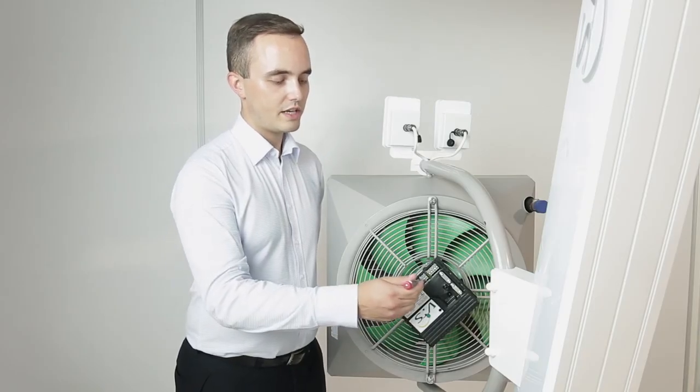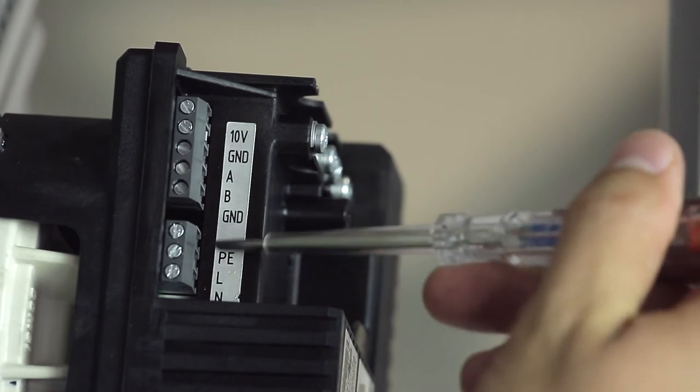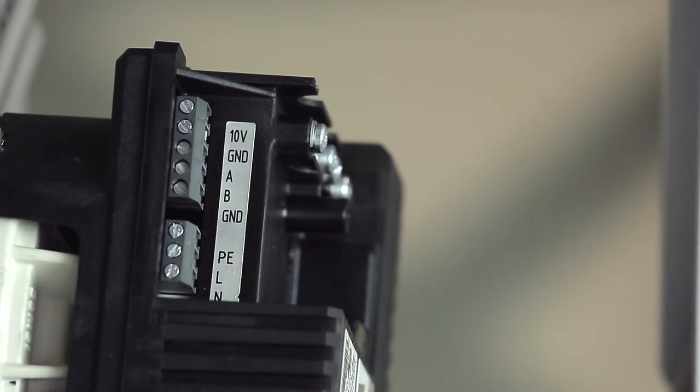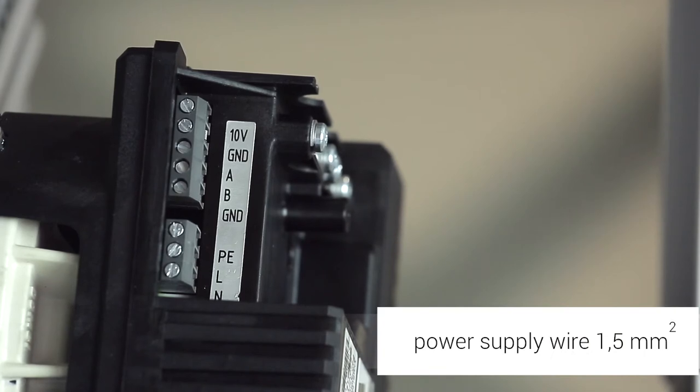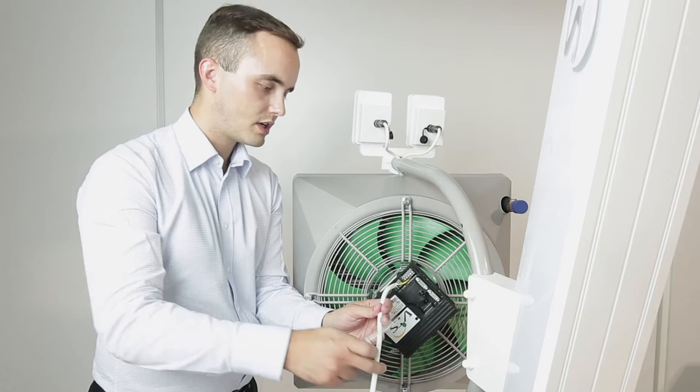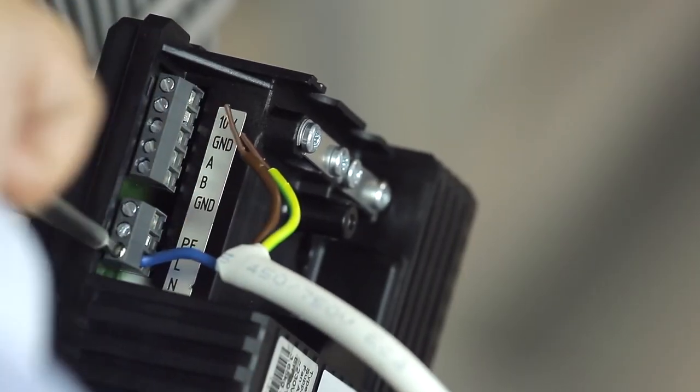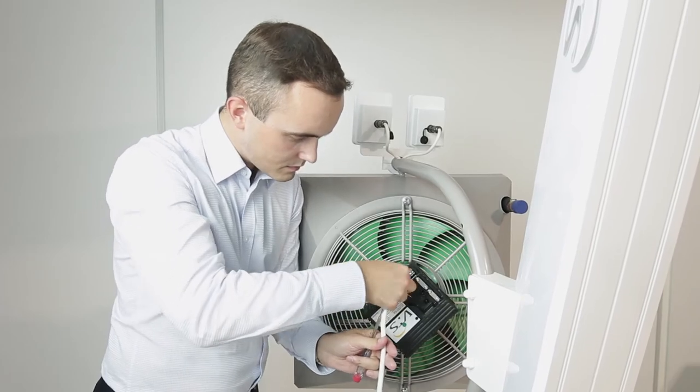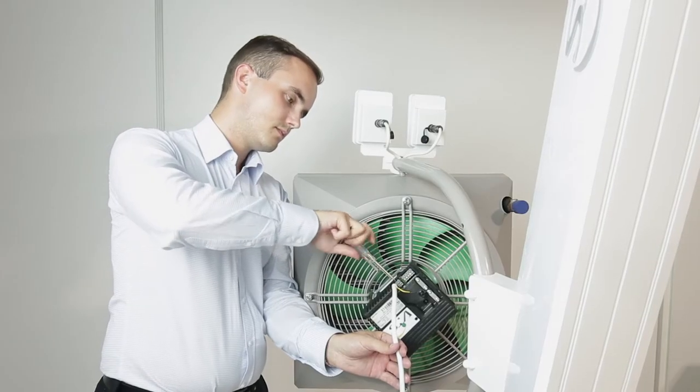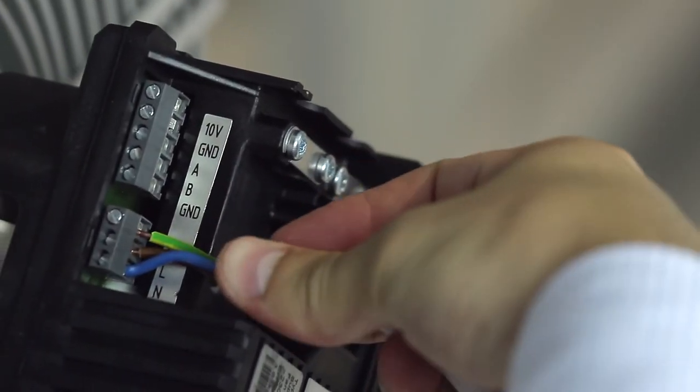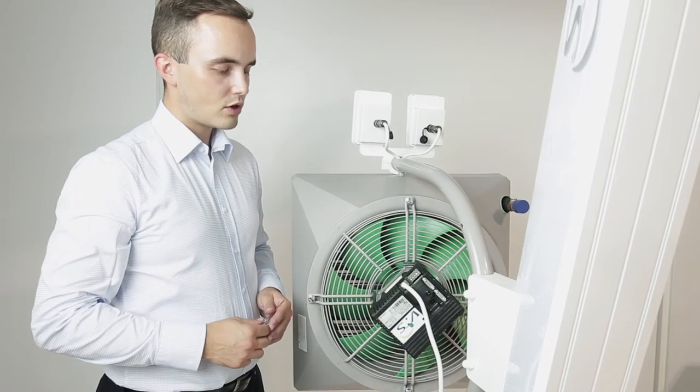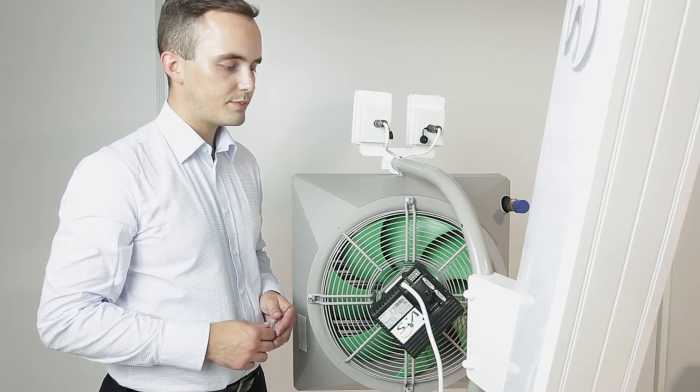Now let's connect the single phase power supply. The recommended wire diameter is 1.5 millimeters squared and with these wires we will now connect our engine. Neutral wire, phase wire, and ground wire. At this point we have completed the single phase power supply connection.